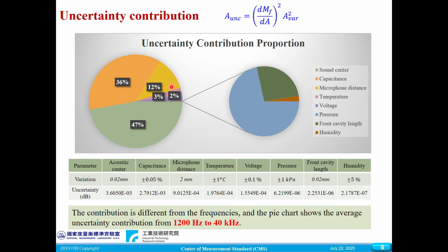This breaks the rumor that the pressure varies a lot during calibration and will cause much uncertainty in the experiment. In fact, it only possesses a portion below 1 per thousand, for it's at 6 decimal places.